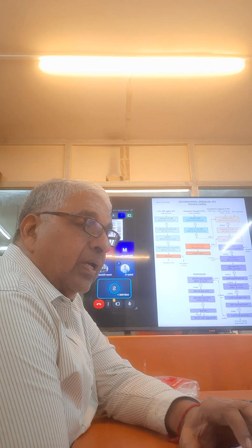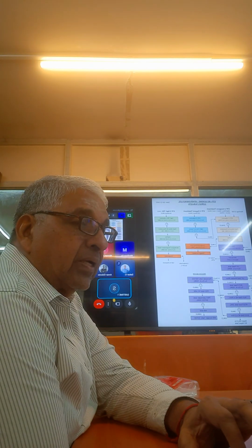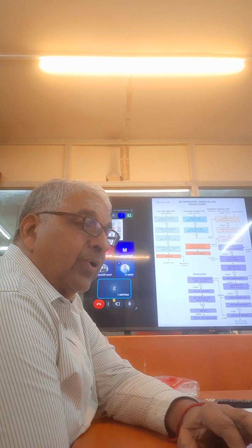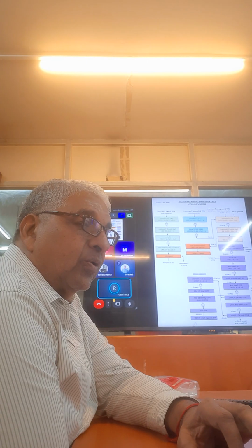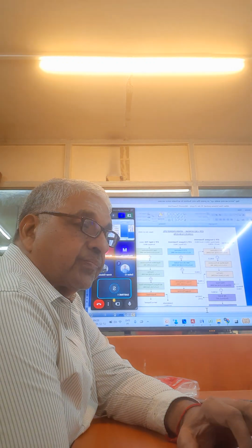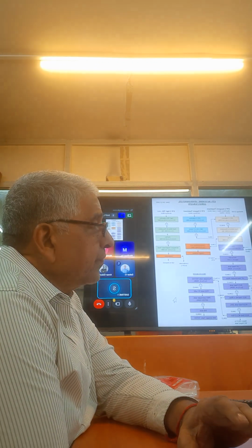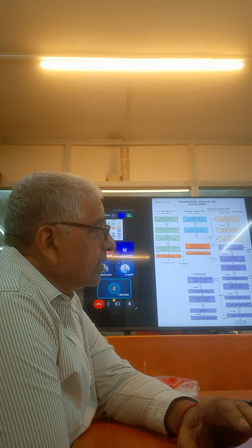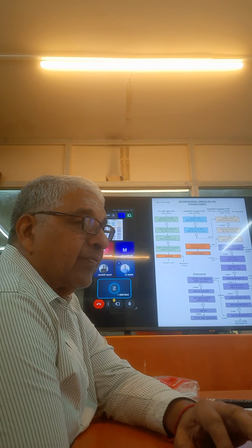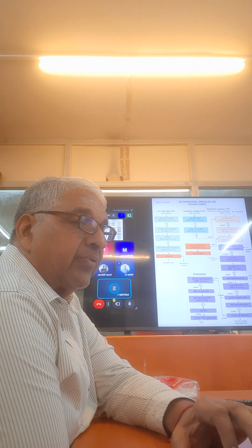This way you will have a fairly steady operation. And since you have to go for evaporator, if you feed the permeate directly into DM MB, you will be regenerating almost every other day. That means 100 kg of salt will be generated unnecessarily. So here you will be saving that, your load on the evaporator, everything.